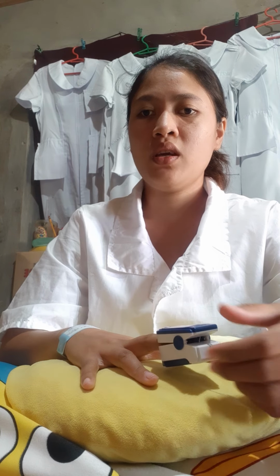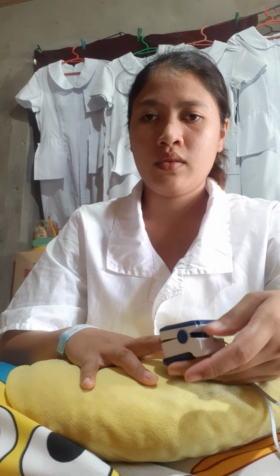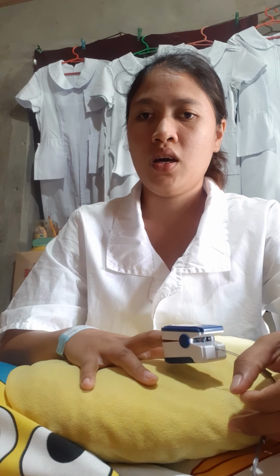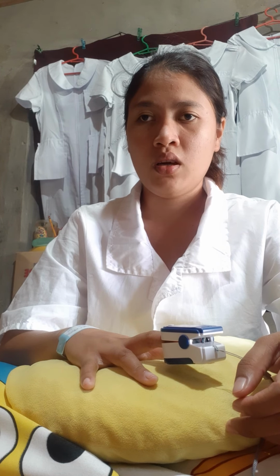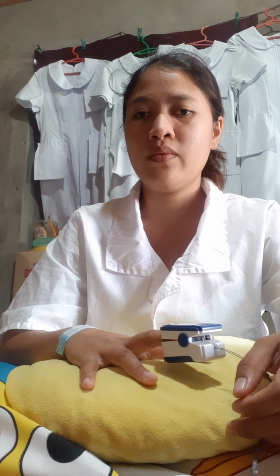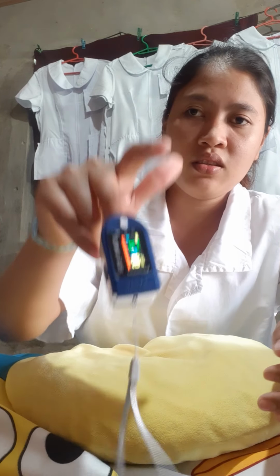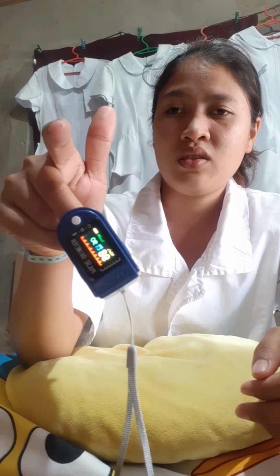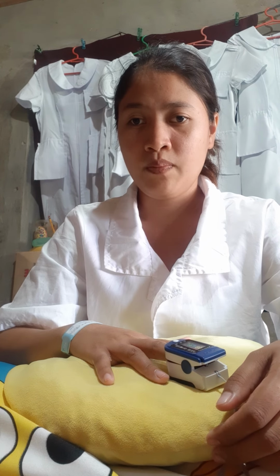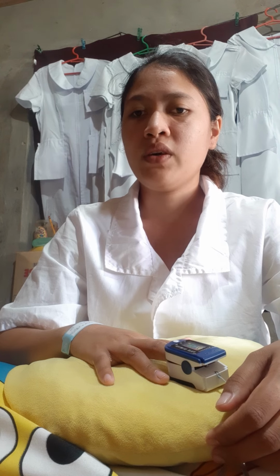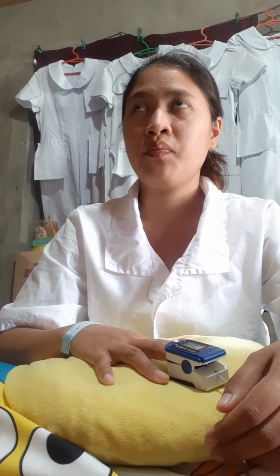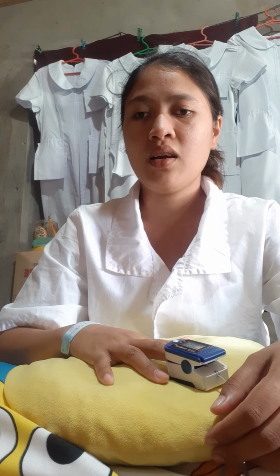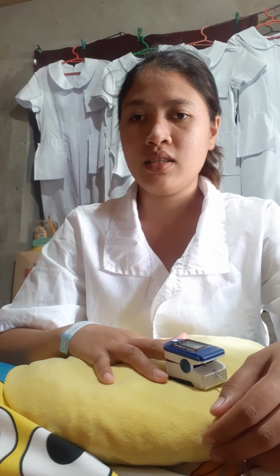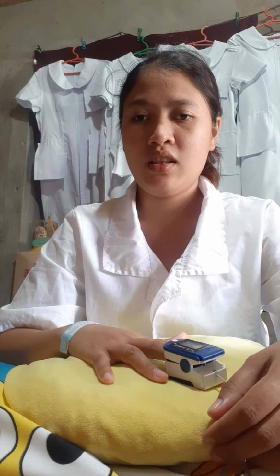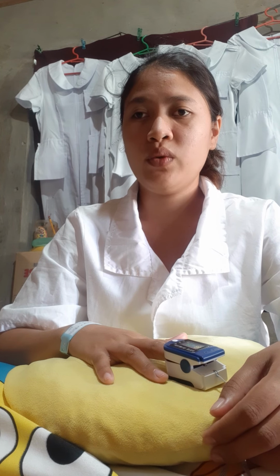Then we need to turn on the pulse oximeter and check the beeping sounds, fluctuation, bar lights, or waveform on the face of the oximeter. But in this oximeter, we hear no beeping sound. So let's proceed. We need to set alarms on the pulse oximeter if possible. Then check the manufacturer's alarm limits for the low and high pulse rate setting. Next, check the oxygen saturation at regular intervals as ordered by the physician. Then heed the signal by alarms, and we need to monitor the hemoglobin level.